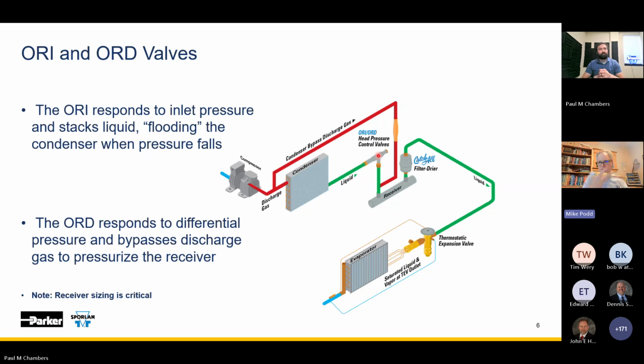Yes. So now the same configuration of valve is used as evaporator pressure regulators, an ORI, open on rise of inlet. It would just have a different pressure setting, with different springs internally. So if you're going to buy one of these things, for sure, do not take an EPR. You've got to be specific on the pressure rating. So don't just replace with an ORI.